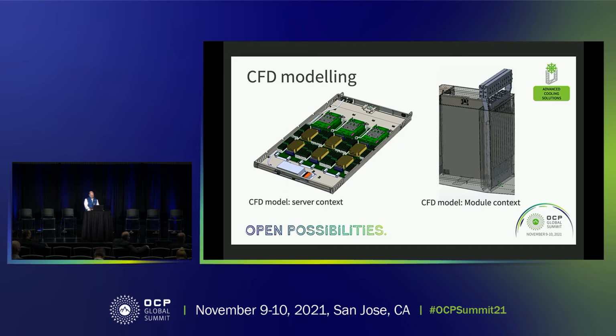The module is the tank that we showed in the earlier slides. The reason for that is because we don't only have heat sources and flow impedance at the server scale, but we also have the same at the module scale too. So there's a cooling source which increases density, but also presents flow impedance alongside the server. So we model our servers in the module in order to give a full digital twin representation of the server in context of how it is cooled.